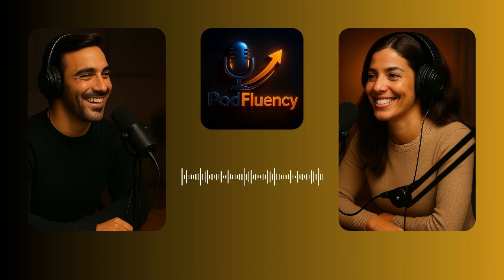Okay, two more equipment categories to cover, and then we can move on to how all this stuff gets connected together. Next up are capacitor banks. What are those all about? Capacitor banks are primarily used for what's called power factor correction. Sounds a bit technical. It is, but the basic idea is this. AC electrical systems have two types of power. Real power, which is what actually does the work, like running your appliances, and reactive power, which doesn't directly do work but is needed by certain types of equipment to operate correctly. Think of reactive power as the froth on top of a beer. It takes up space but doesn't contribute to the actual beer you can drink. And this reactive power can cause problems in the electrical system by increasing current flow and losses.